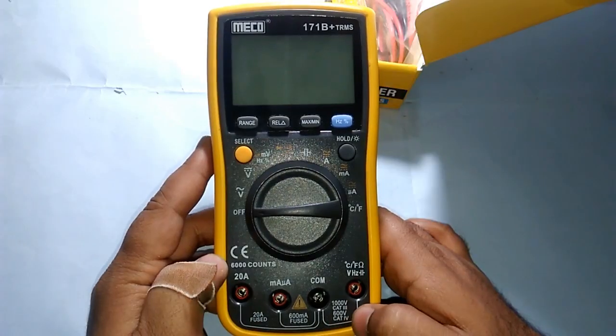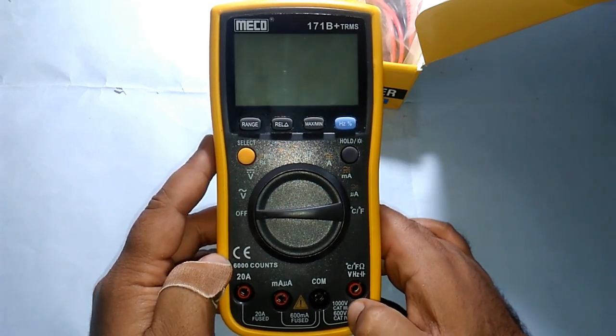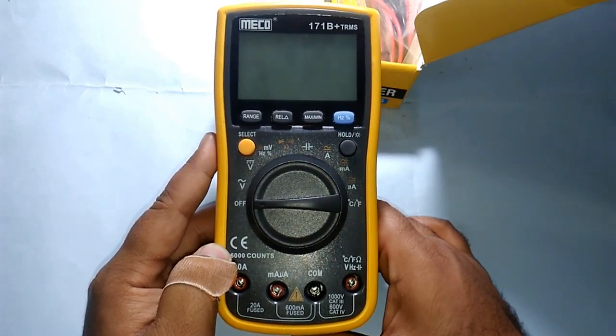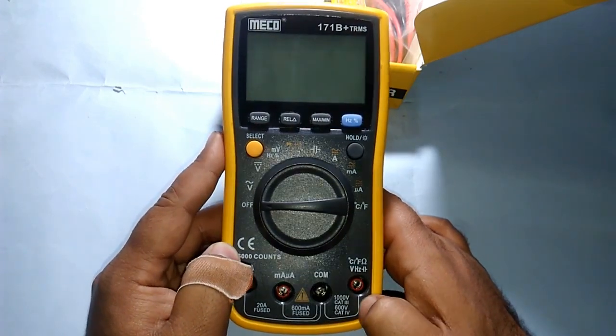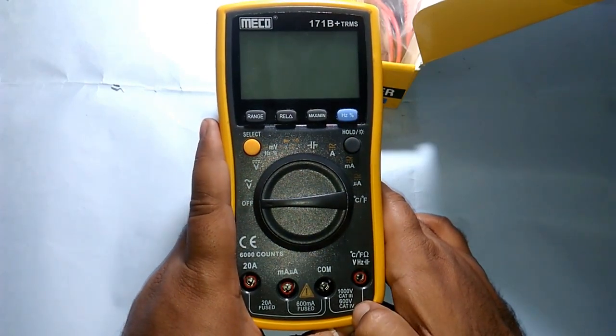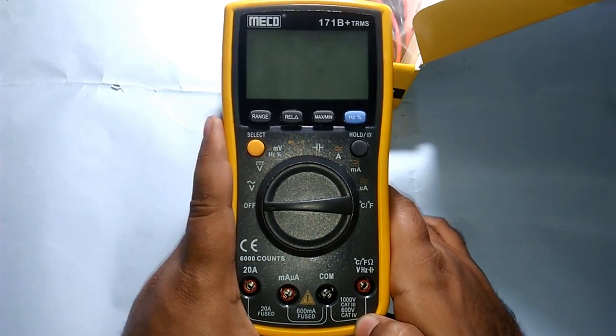You can see this multimeter is CAT4 approved at 600 volts and CAT3 approved at 1000 volts. CAT3 and CAT4 are category 3 and category 4 standards for electronic testing devices. CAT4 is the highest level of security and CAT1 is the lowest, so if it says CAT4, you know it's an industrial grade multimeter.